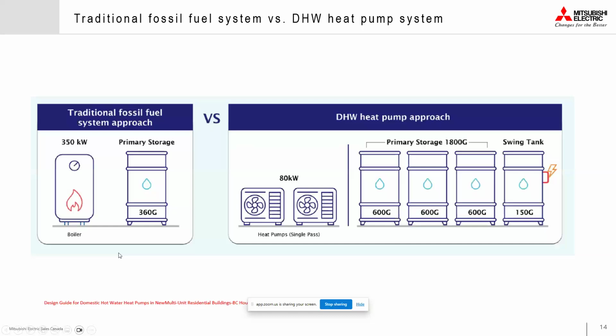So that's the, I think, picture tell you the whole story, the 1,000 words. On the left side, you get the traditional fossil fuel system like a gas boiler. You have a higher capacity of 350 kilowatt and only storage with 360 gallon for it. And the same building, if you want to replace with a heat pump, as I mentioned in the previous slide, we want to reduce the capacity as much as possible to reduce the initial cost.